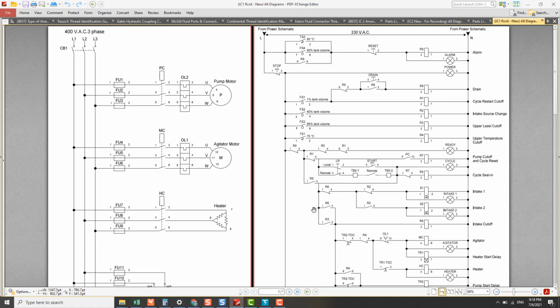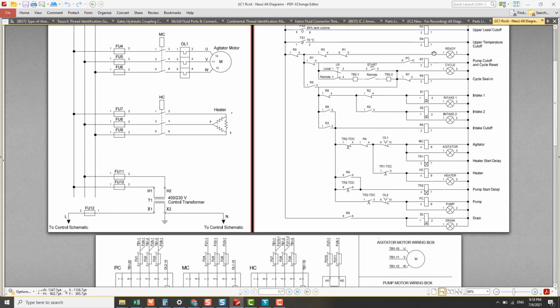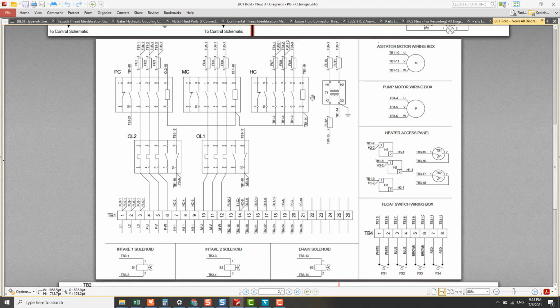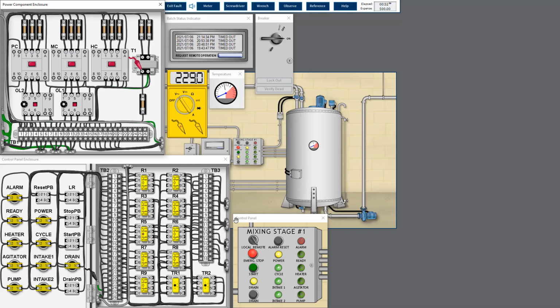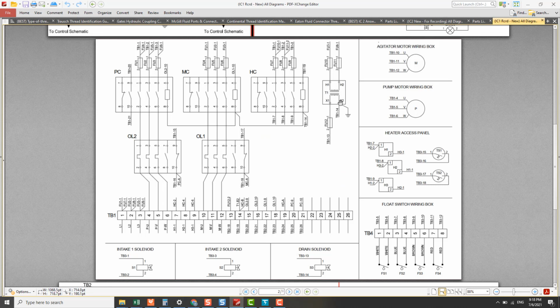The easiest way to check for any slightly loose connection or a load with slightly high resistance is by checking the common neutral line from the transformer side. I start from T1X2, the transformer terminal, which is connected to TB114 here. 0 volt is correct, because the ground point, the earth point, is actually connected to the neutral point of the transformer. So the voltage across the neutral line, which is just a wire, must be 0. It cannot register any voltage. This is the correct one.